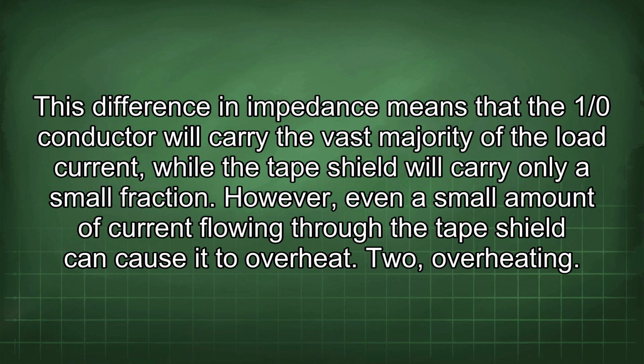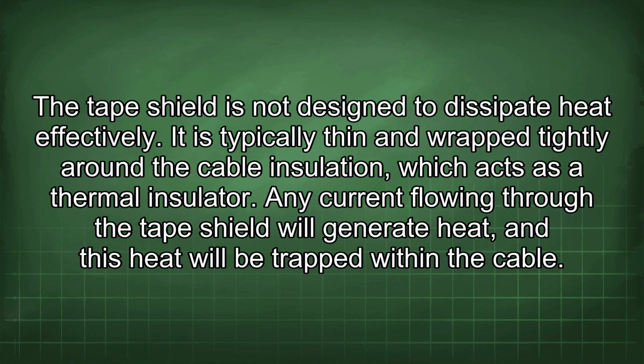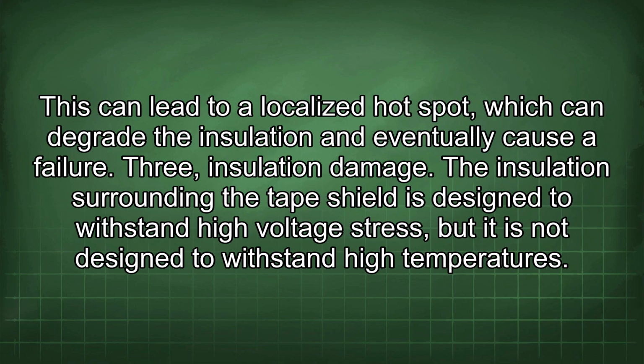2. Overheating. The tape shield is not designed to dissipate heat effectively. It is typically thin and wrapped tightly around the cable insulation, which acts as a thermal insulator. Any current flowing through the tape shield will generate heat, and this heat will be trapped within the cable. This can lead to a localized hotspot, which can degrade the insulation and eventually cause a failure.